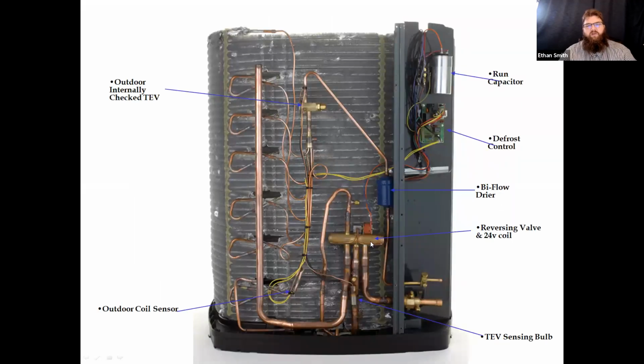Okay, so there's a cutaway of a Trane or American Standard unit. We can see our reversing valves over here. We've got a biflow filter dryer right here. We now have an outdoor TXV because in the heating mode, this does act as an evaporator. So we're going to need to meter refrigerant into it.